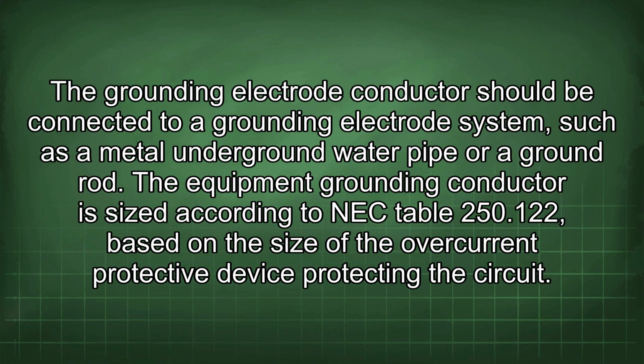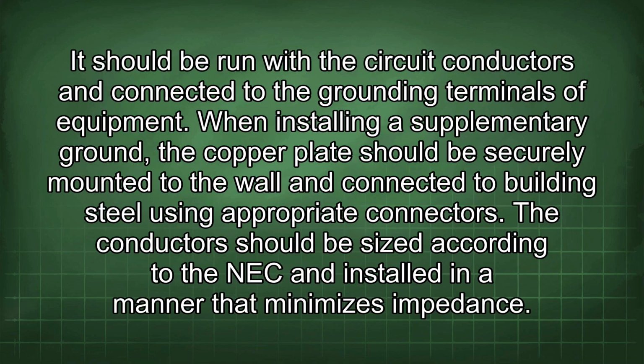The grounding electrode conductor should be connected to a grounding electrode system such as a metal underground water pipe or a ground rod. The equipment grounding conductor is sized according to NEC Table 250.122 based on the size of the overcurrent protective device protecting the circuit. It should be run with the circuit conductors and connected to the grounding terminals of equipment.